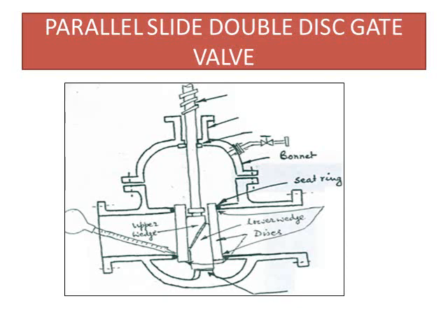You can see in this valve particularly a sealant adapter valve is provided in the bonnet of the valve, from where externally you can pressurize the bonnet through water or any other liquid to engage the discs in a pressurized condition with the seat. So there shall be minimum leakage out and passing of the valve.